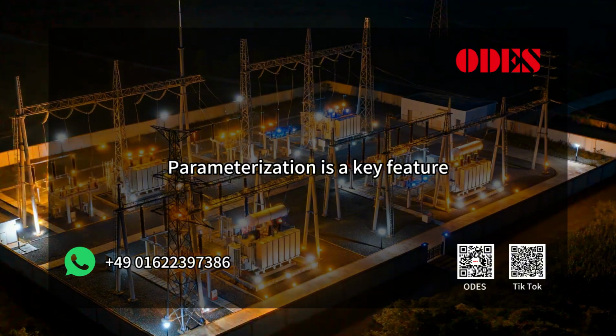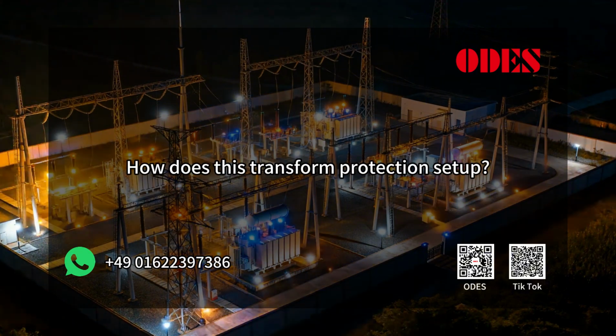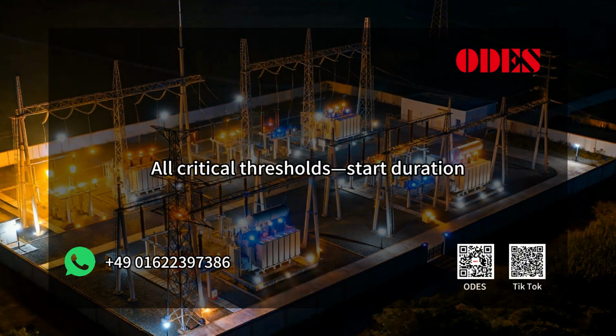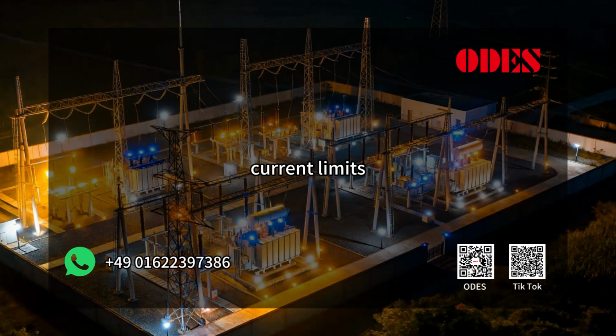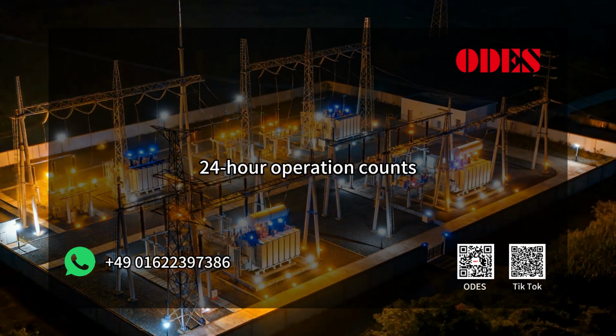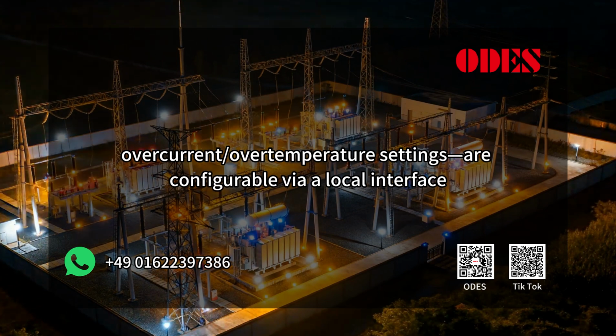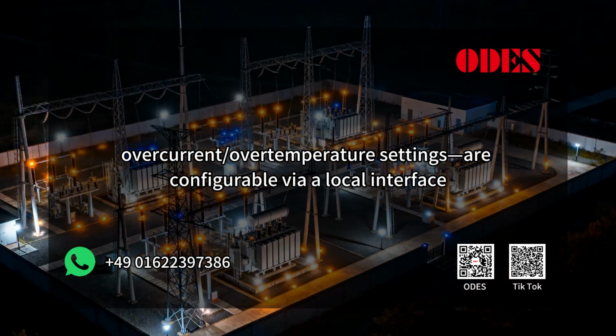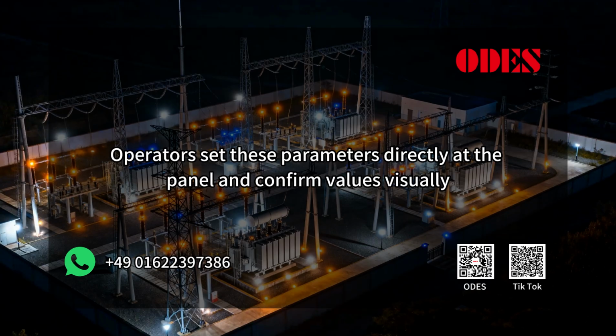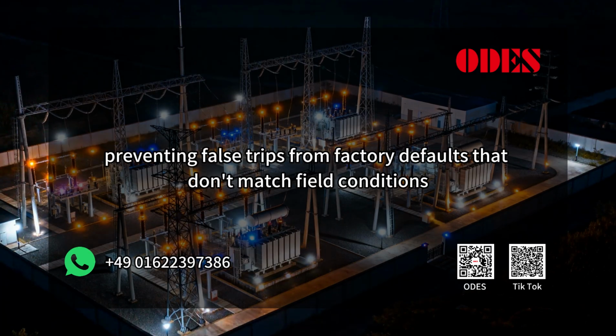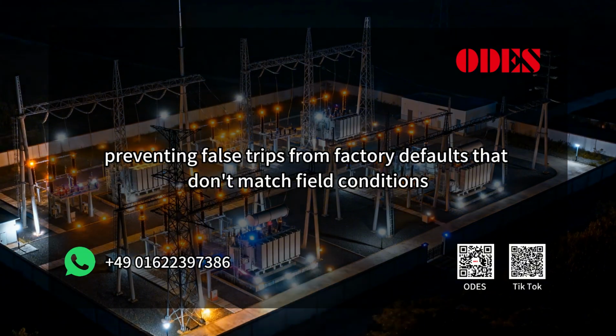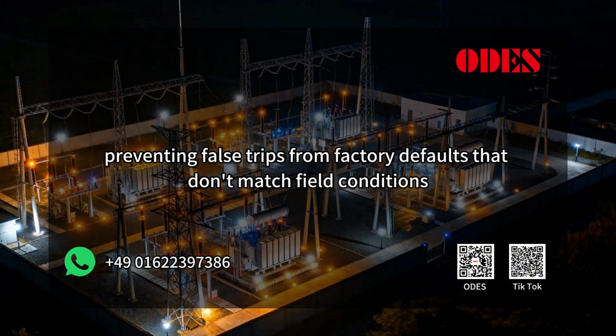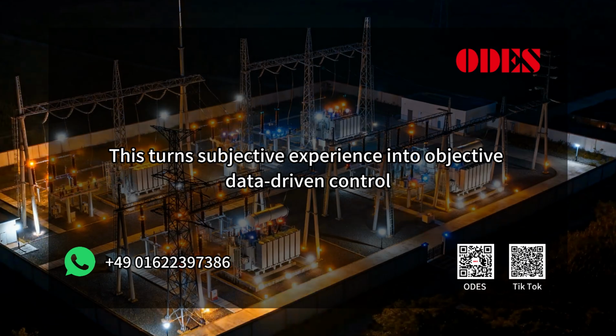Parameterization is a key feature. How does this transform protection setup? All critical thresholds, start duration, current limits, 24-hour operation counts, overcurrent over-temperature settings, are configurable via a local interface. Operators set these parameters directly at the panel and confirm values visually, preventing false trips from factory defaults that don't match field conditions. This turns subjective experience into objective data-driven control.